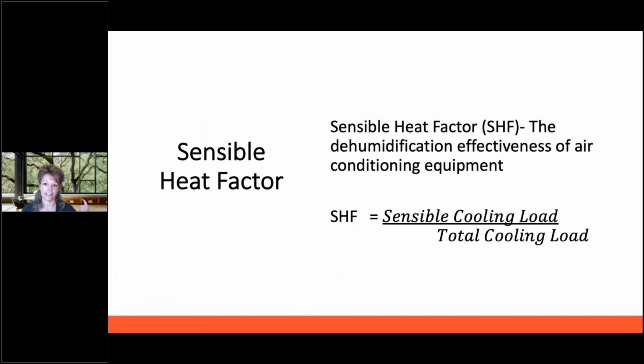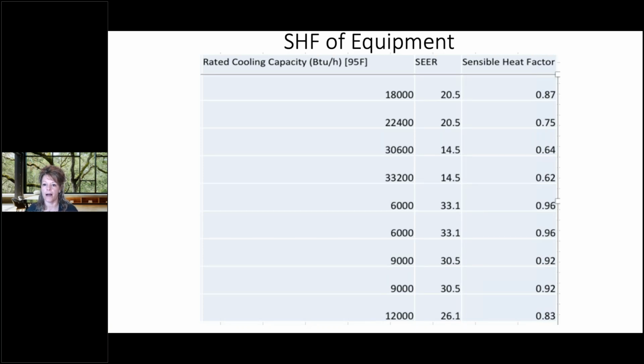So sensible heat factor is something that we are discussing more and more when it comes to designing HVAC systems. We really need to understand how much water that piece of equipment is going to remove when it is running. We need to know our sensible heat factors. So here's a chart of some equipment. We've got a 14 and a half SEER piece of equipment with a 62% sensible heat factor. Meaning when it's running, 62% of the BTUs are focusing on cooling, and the other 38% is focusing on latent removal. So when this piece of equipment's running, it's doing a pretty good job of removing moisture.